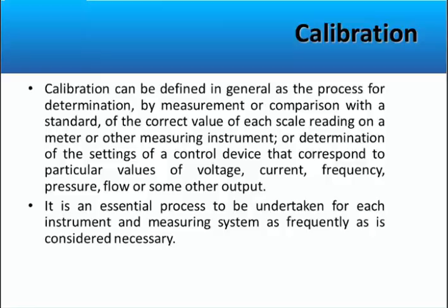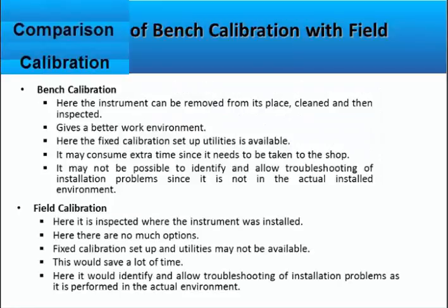Now, the fact that you're taking it out of service means you must put a regular timing aspect to that. It can't just be ad hoc, it has to be at regular intervals. Depending upon the criticality of the system and its environmental conditions such as vibration, heat, temperature, pressure and humidity, it may require more frequent verification steps and checks, but a yearly period is one that is common. So, as I said, there are different aspects.